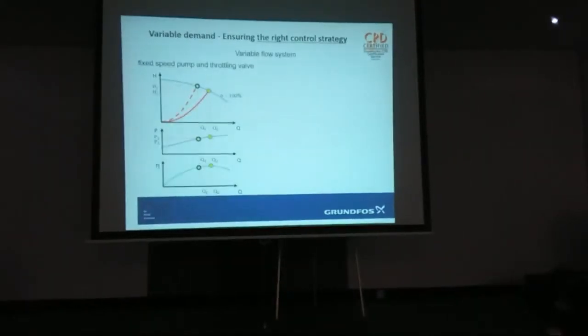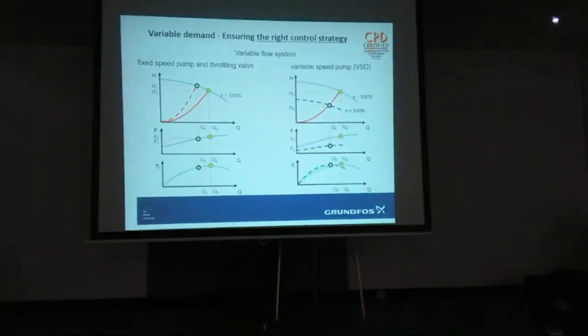The inverter comes into its own when you have situations like this. Normally, in the old days, which wasn't that long ago, a fixed speed pump would work there. Your actual flow rate is here. So you screw a valve shut and it works up there. In reality, you should slow the pump right down to that point there, and then work there. Brilliant. So you've saved all that energy.